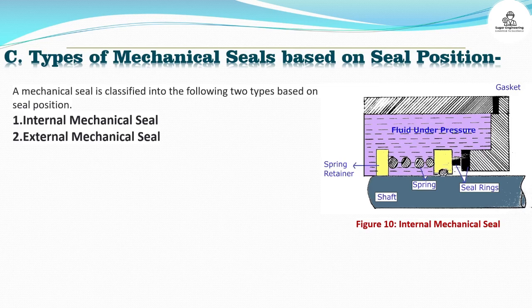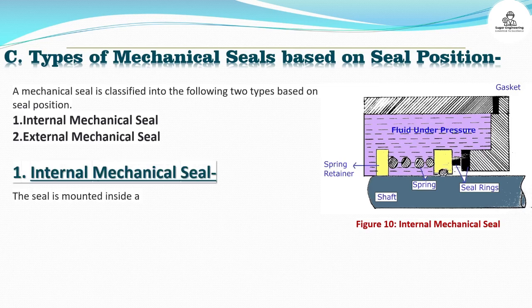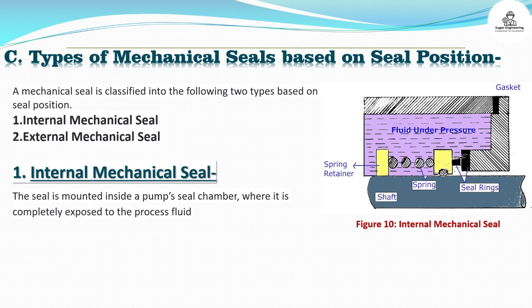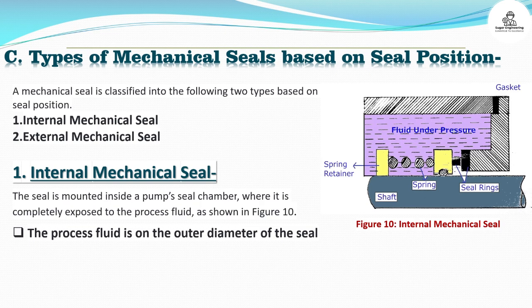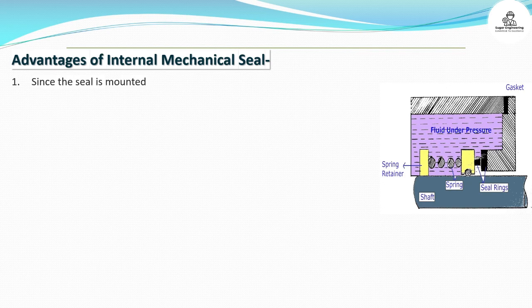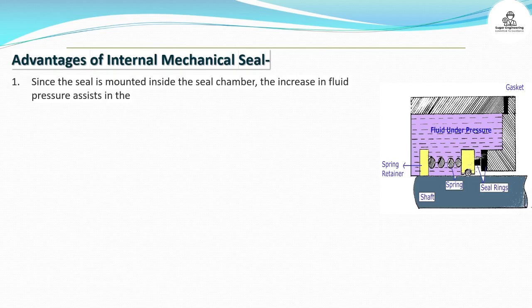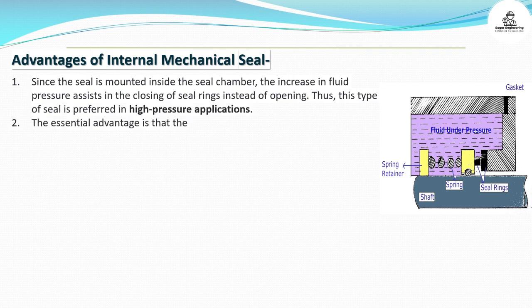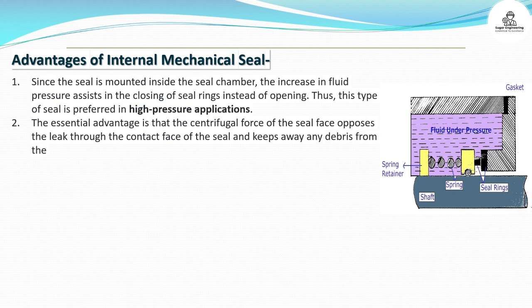Types of mechanical seals based on seal position: A mechanical seal is classified into two types based on seal position — internal mechanical seal and external mechanical seal. Internal mechanical seal: The seal is mounted inside a pump seal chamber, where it is completely exposed to the process fluid, as shown in Figure 10. The process fluid is on the outer diameter of the seal. Advantages: since the seal is mounted inside the seal chamber, an increase in fluid pressure assists in the closing of seal rings instead of opening — thus this type of seal is preferred in high-pressure applications. The centrifugal force of the seal face opposes the leak through the contact face and keeps away any debris from the mating faces. It is also easy to cool the seal since the process fluid surrounds the contact face.